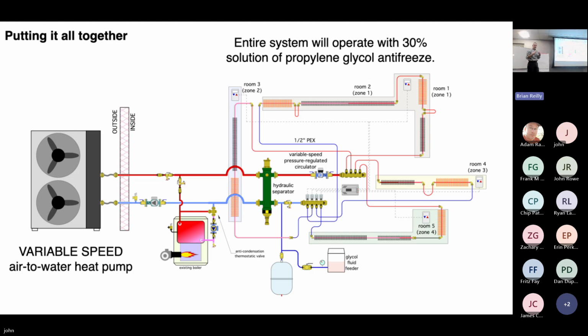I'll tell you what I'd like personally. One multi air handler could do the whole house. I got you. I like the idea of multi-zone heating, single zone cooling for reasonable single family houses. When I say reasonable, 3,000, 4,000 square feet. If you've got a 10,000 square foot house, no, I mean, you know, the average. It's sprawling. You need multiple air handlers for that. But for the average house, I'd like a single. And I'll try to justify that.